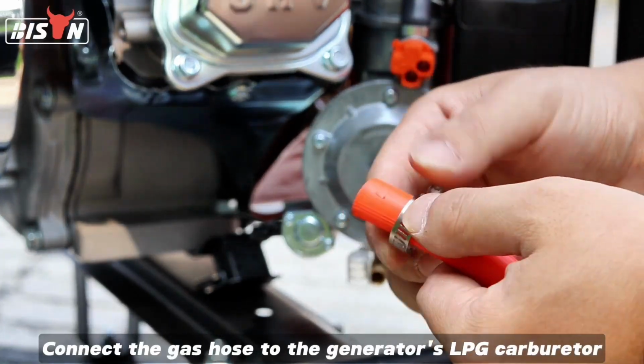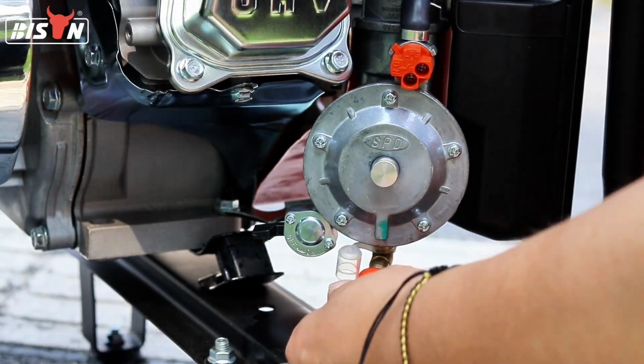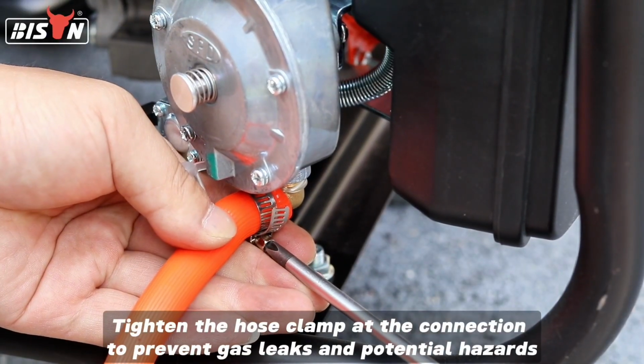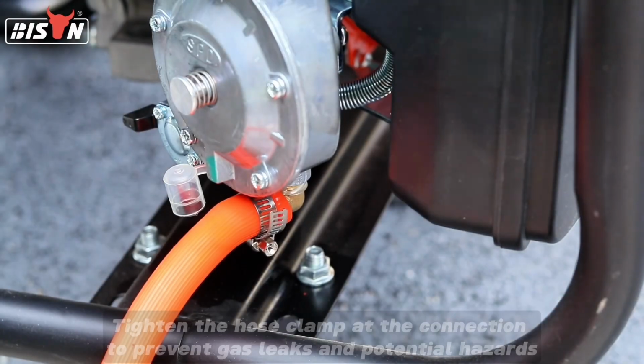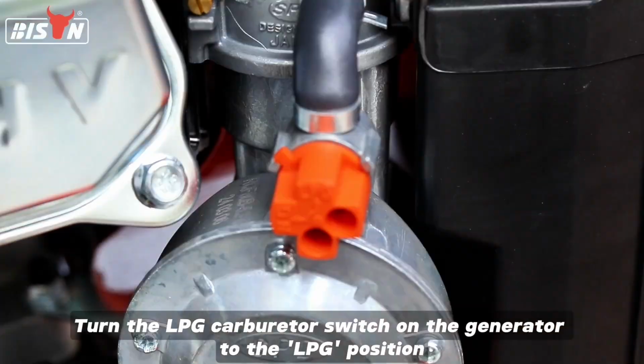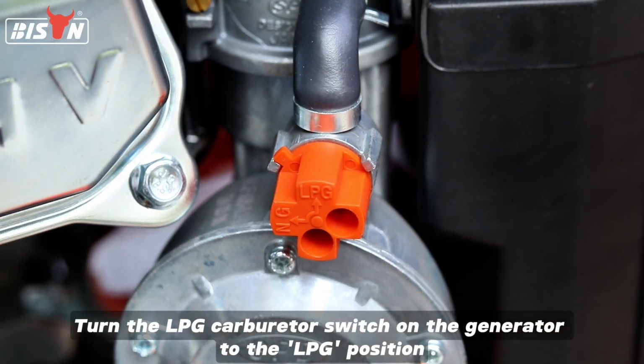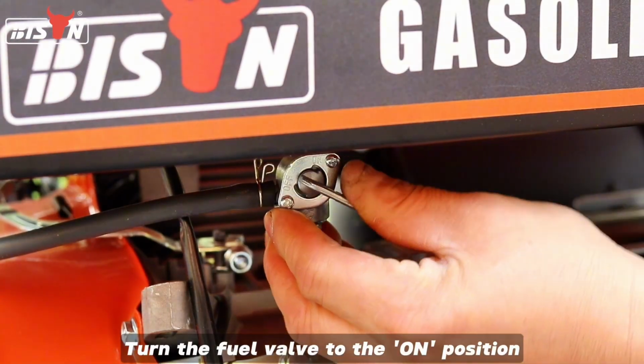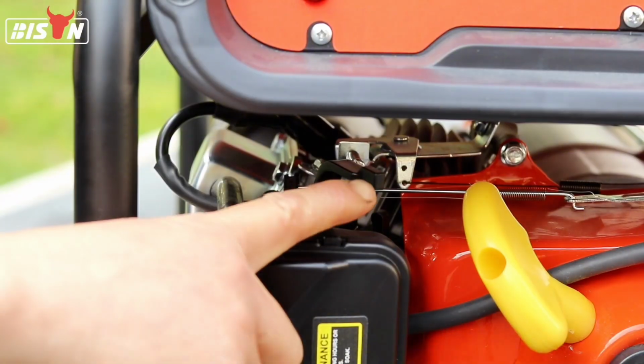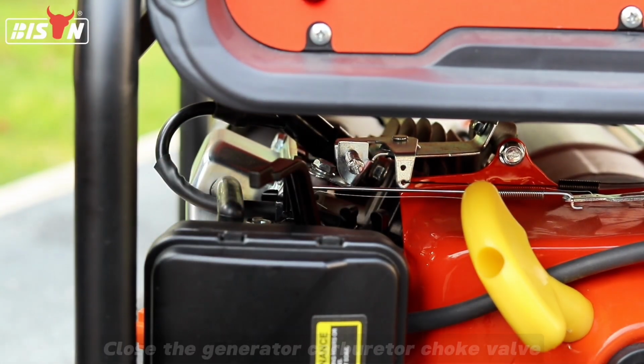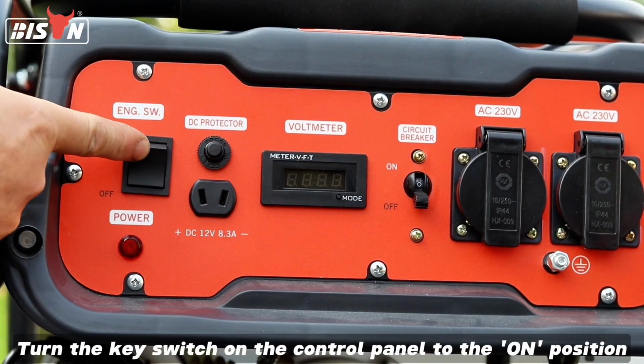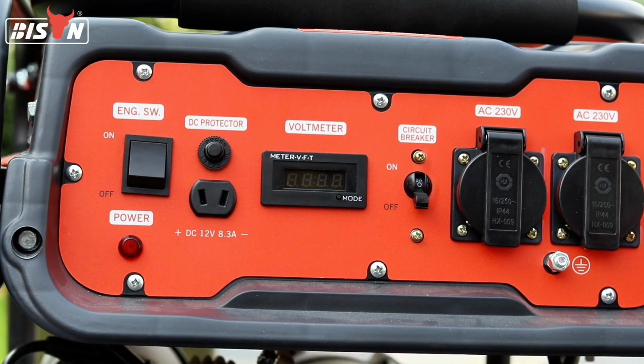Connect the gas hose to the generator's LPG carburetor. Tighten the hose clamp at the connection to prevent gas leaks and potential hazards. Turn the LPG carburetor switch on the generator to the LPG position. Turn the fuel valve to the on position. Close the generator carburetor choke valve. Turn the key switch on the control panel to the on position.